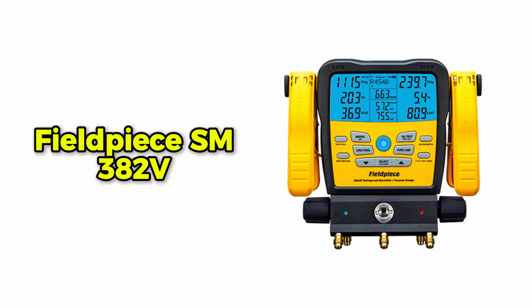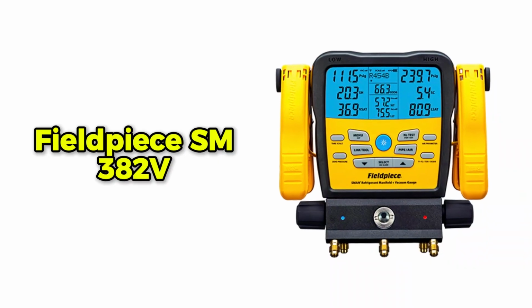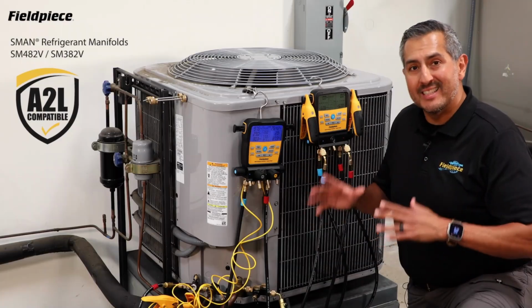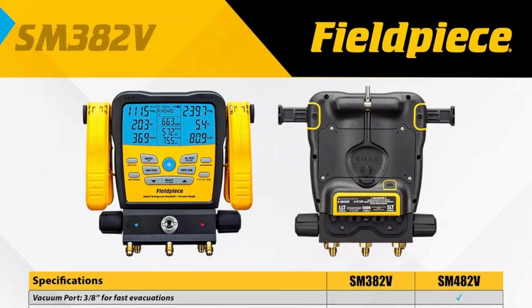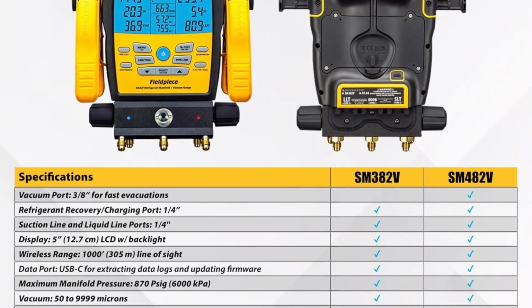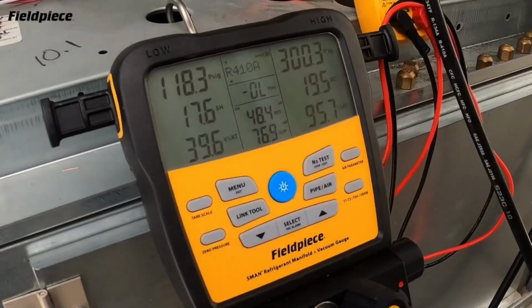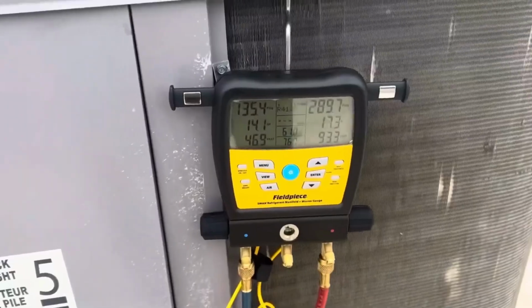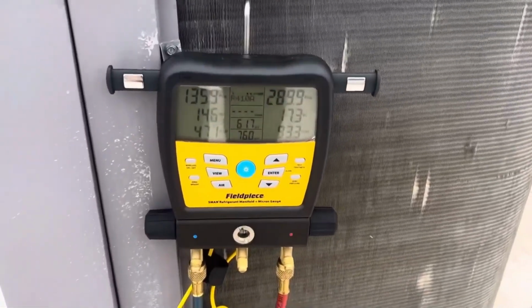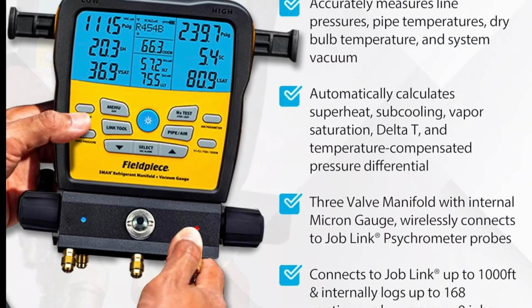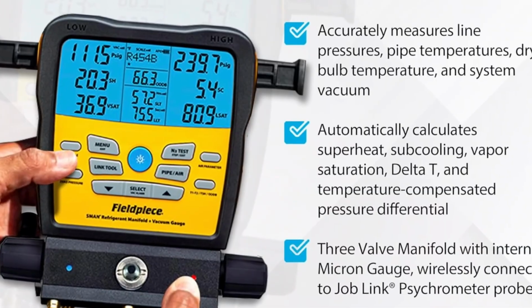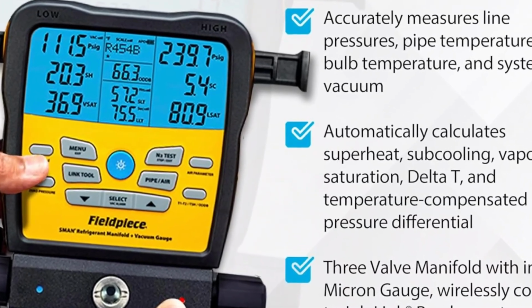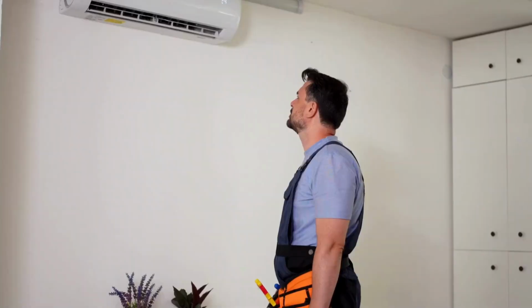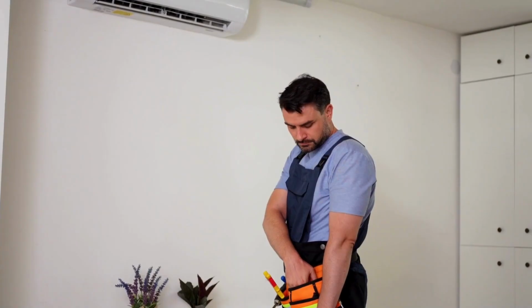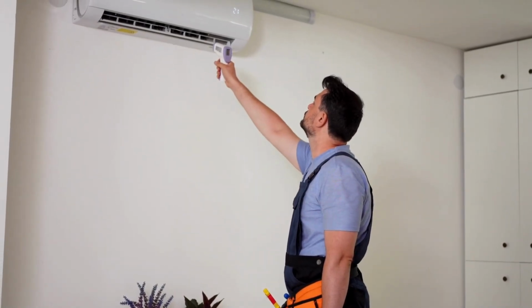Number 1 on our list is the Fieldpiece SM382V digital manifold. This model is one of the most sophisticated and advanced options available if you want total control of the system without any cables. It is specifically designed for technicians who perform comprehensive HVAC maintenance, diagnostics on complex systems, or frequent calibrations. Real-time digital pressure reading. One of its main advantages is that you don't have to interpret analog scales. The digital display shows you exact values for positive and negative pressure, which reduces common errors in diagnosing systems with refrigerant loss or internal failures.